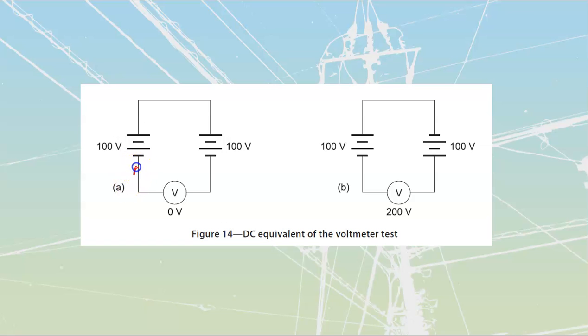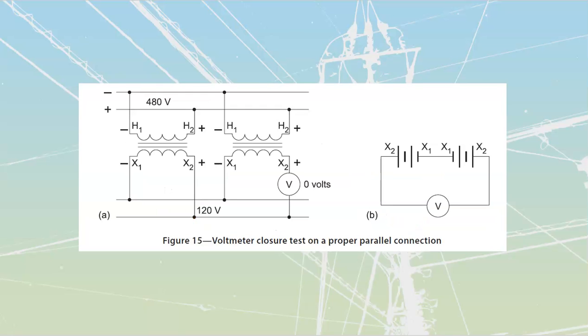Same as before: if my connection is correct, in other words if I've got all the polarities lined up, I should see 0-ish volts. If I have improper polarity, I'm going to see double the value of voltage. Now practically speaking, there's going to be a little bit of induction, and we'll see some small differentials. But we'll be able to identify for sure when we've got a bad connection. Anything that's not a full bad connection, we can assume would have to be the good type of connection.